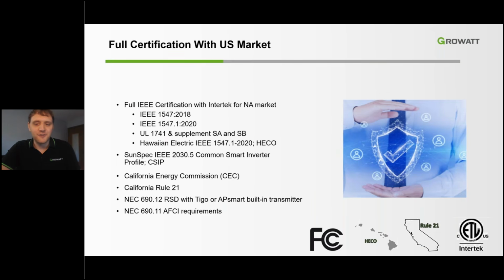So the MIN TL-XH inverter is fully certified with the North American market. The MIN has been certified with Intertek for IEEE 1547 2018 and IEEE 1547.1 for the Hawaiian Electric Grid, or HECO. We are certified in both supplements of the UL 1741 standard, SA and SB. We are also Common Smart Inverter Profile certified with SunSpec IEEE 2030.5 and are compliant with the California Energy Commission. Lastly, we are compliant with Rule 21 of California, have features of NEC 690.11 AFCI requirements, and feature NEC 690.12 rapid shutdown compliance.